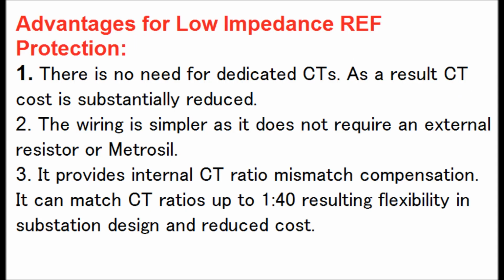Advantages of low impedance REF protection. Number 1 is there is no need for dedicated CTs. For example, if the phase CT or bushing CT ratio is 600 by 1, then if I use an NCT of ratio 100 by 1 or 200 by 1, all the calculation of the CT ratio correction will be done in the relay. So the CT cost is substantially reduced, that is, the NCT ratio is lower than that required for the high impedance REF relay. So the cost of the CT is reduced.